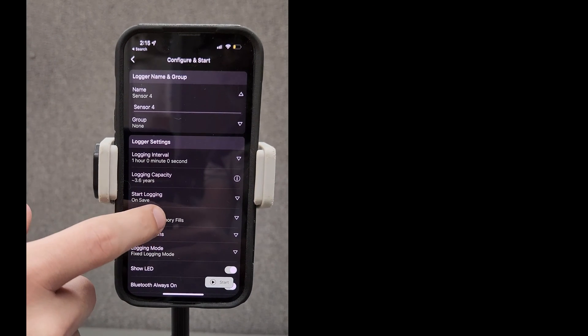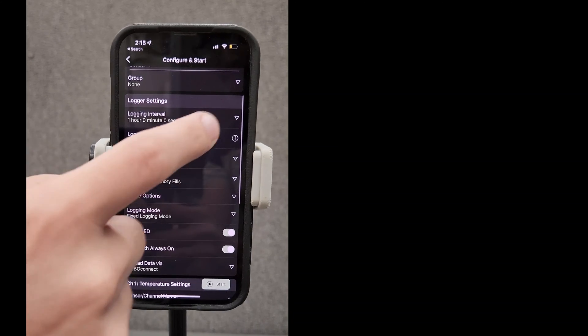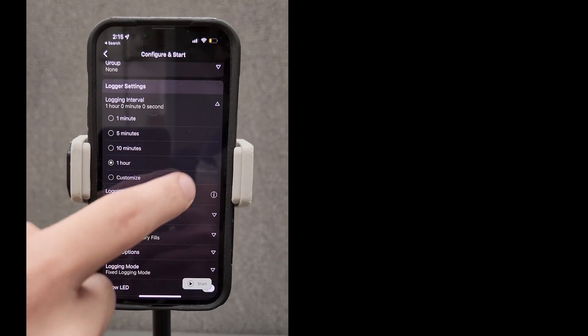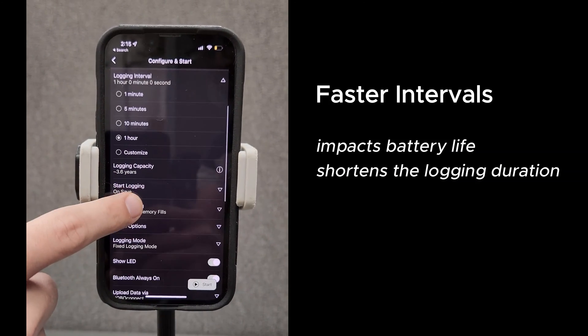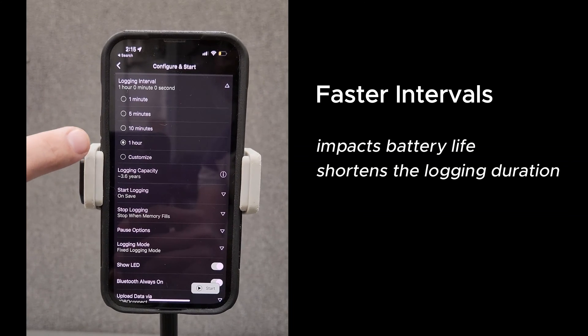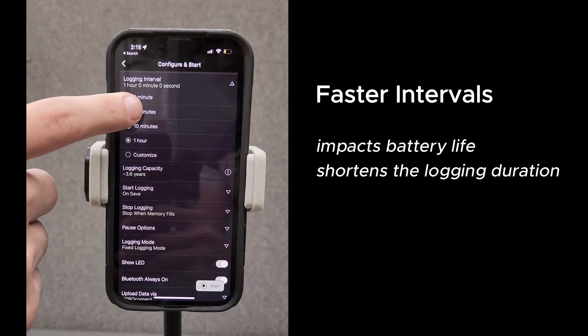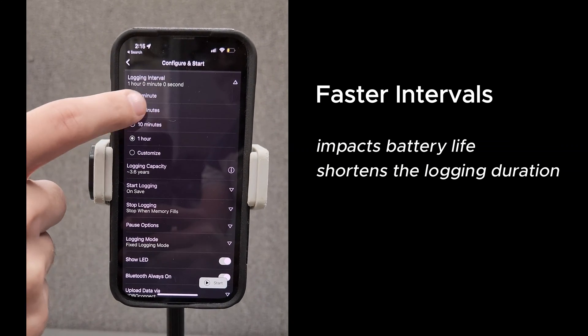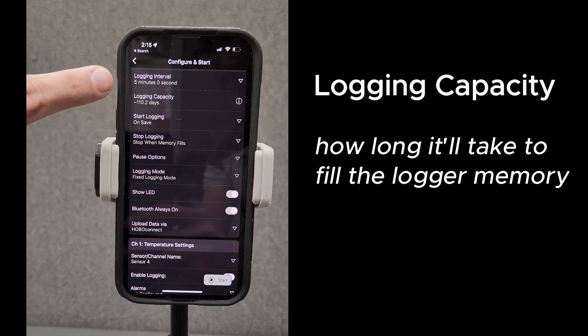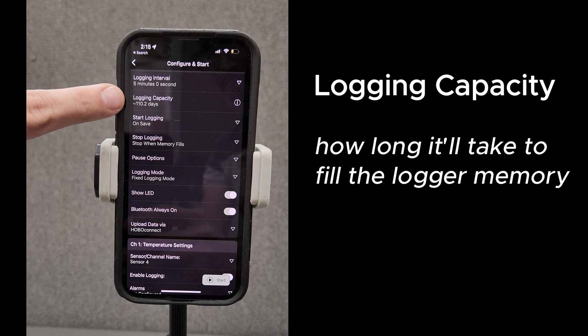Next, you can set the logging interval, which determines how often the logger takes measurements. Keep in mind, a faster interval impacts battery life and shortens the logging duration. The logging capacity indicates how long it'll take to fill the logger memory, based on the logging interval and other factors.